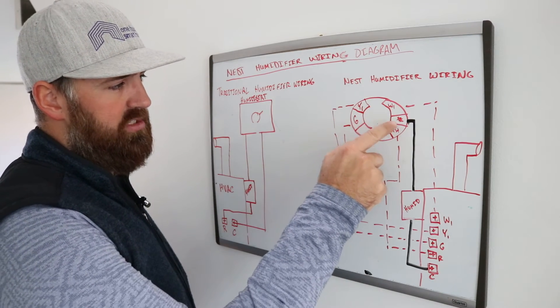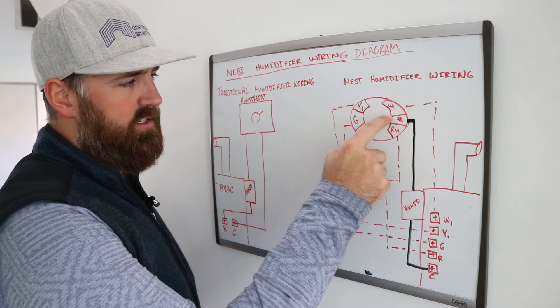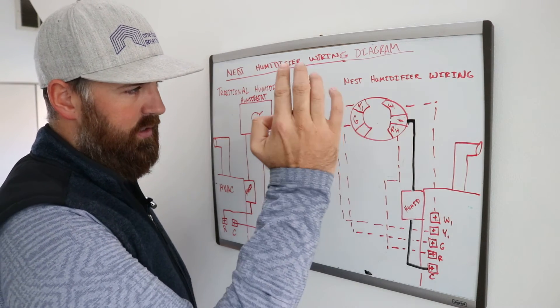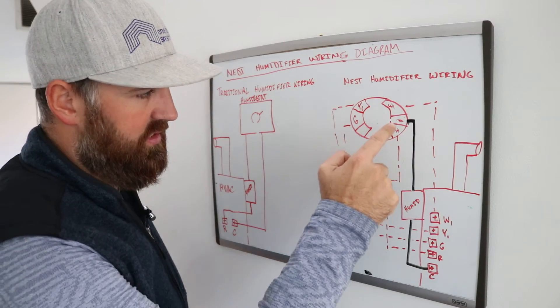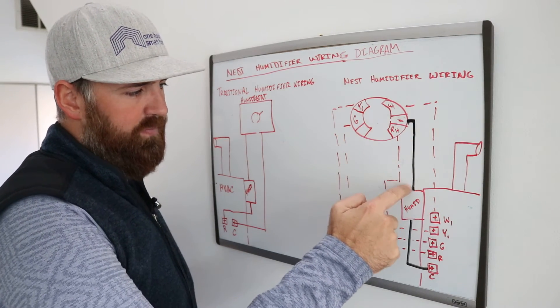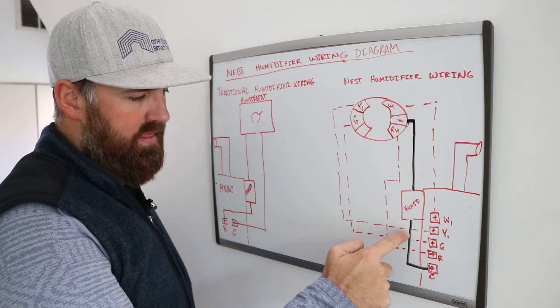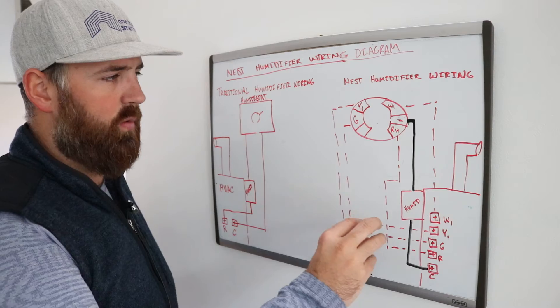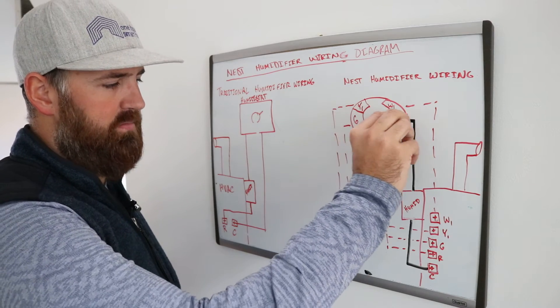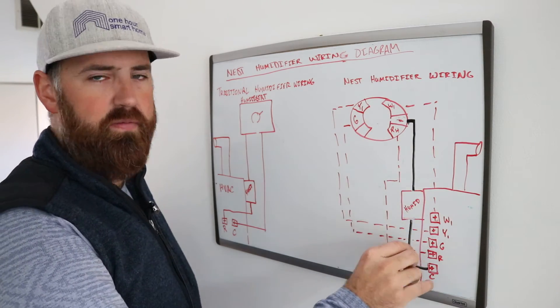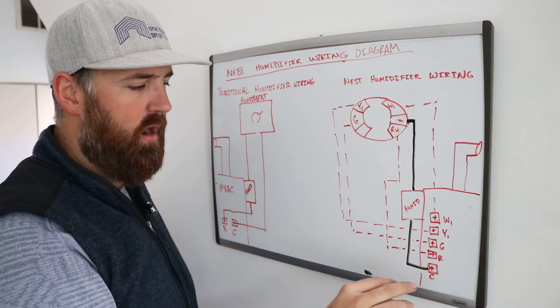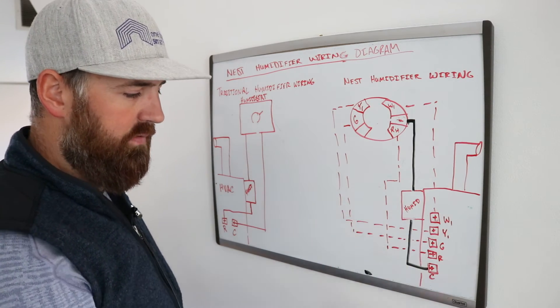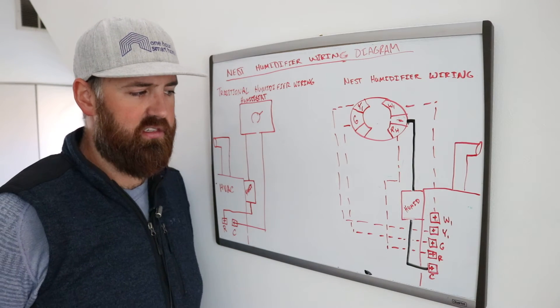So what happens is a switch inside the Nest closes and it shoots power down through this star terminal, which I just erased with my hand but imagine it's there, down through the star terminal, through the humidifier and then on the other side of the humidifier you need to have it connected to a C wire. And what that does is it creates a circuit where the 24 volts from the thermostat will be sent through the humidifier to activate the humidifier and it's got a return path to the circuit board on the C of the HVAC system.